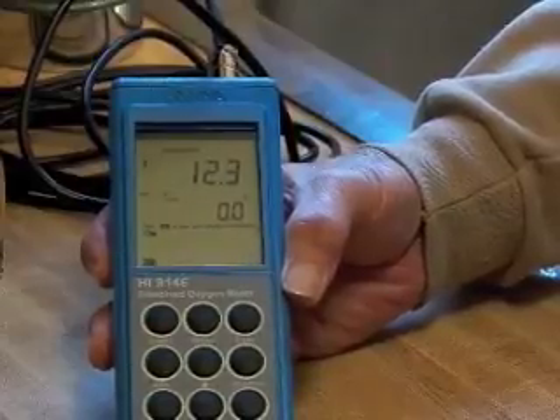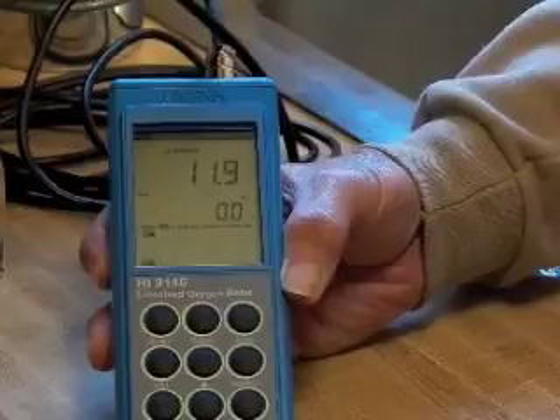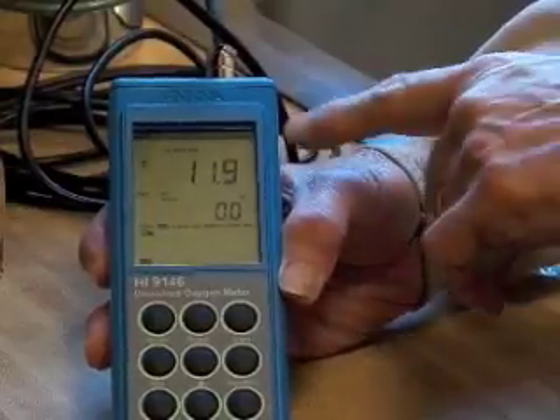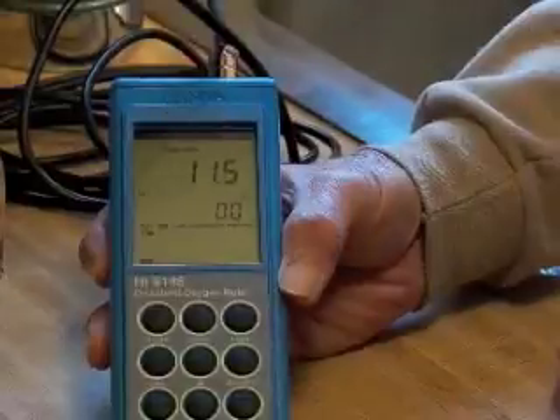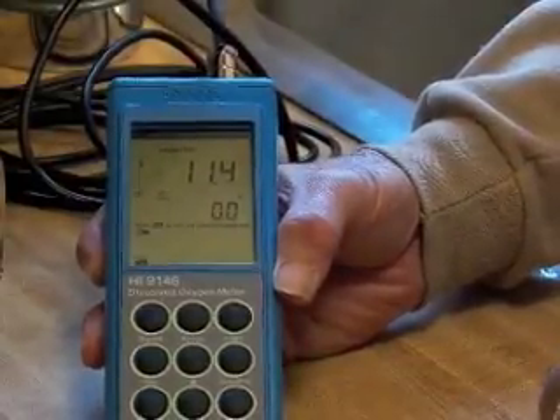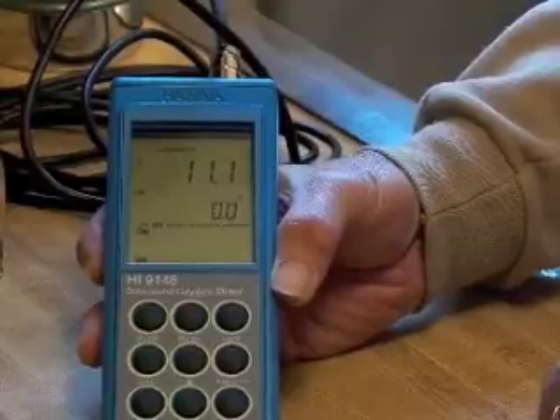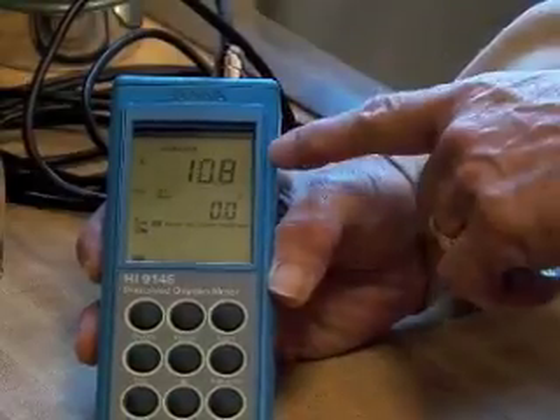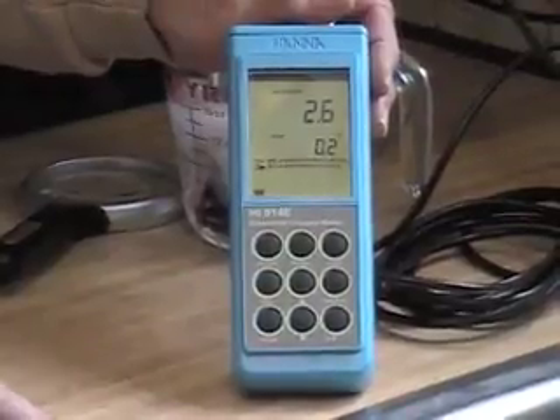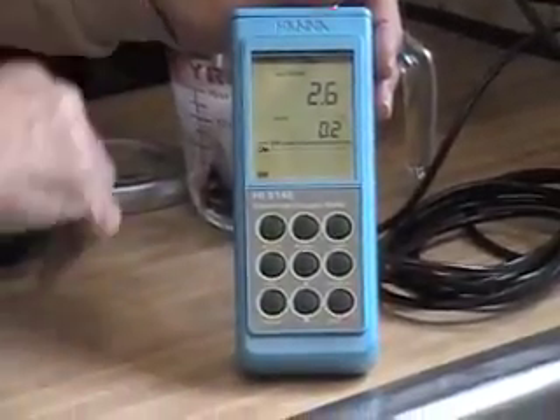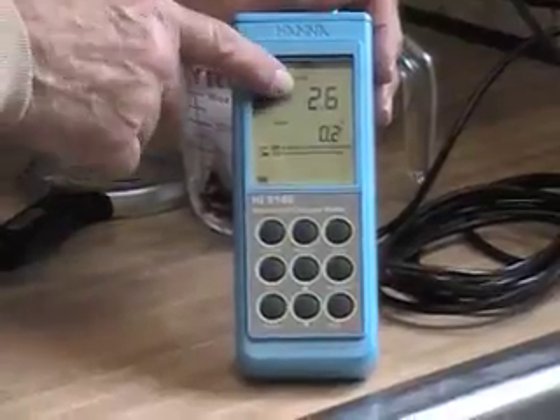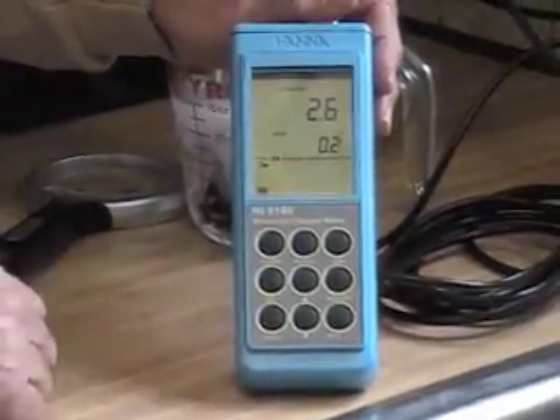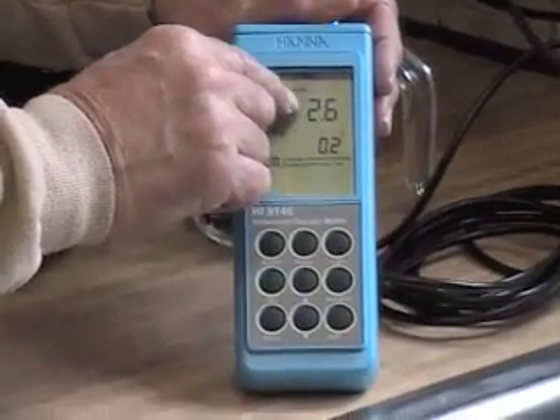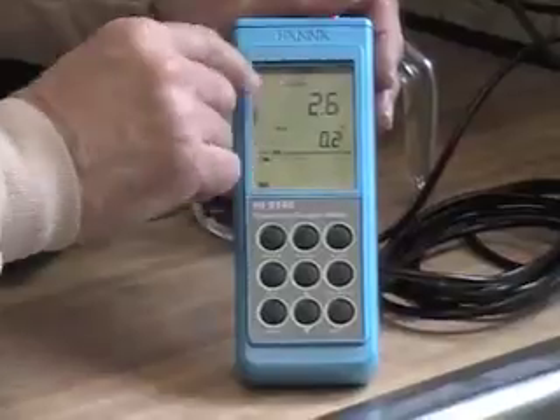It can take about a half hour to go through this process, depending on how picky you want to be and how close to the actual temperature of that water you want to be. But you're just going to have to be patient and wait for the temperature to drop. And you can see it's not happening real fast. Alright, so we've waited about a half hour for the meter temperature to reach the actual temperature of the water, and it's about 2.6 degrees, and that's what I'm reading here.